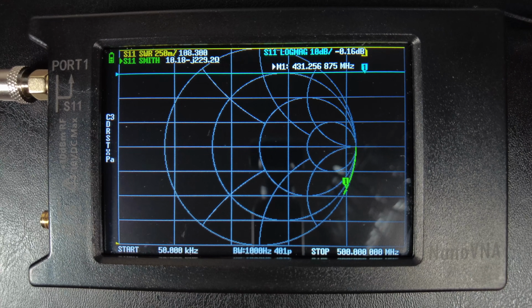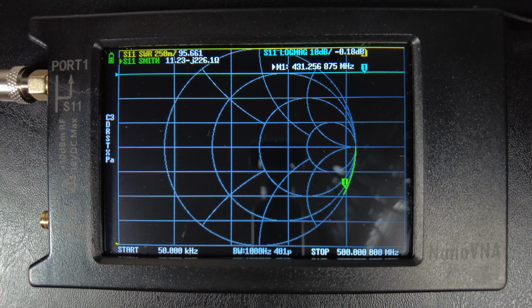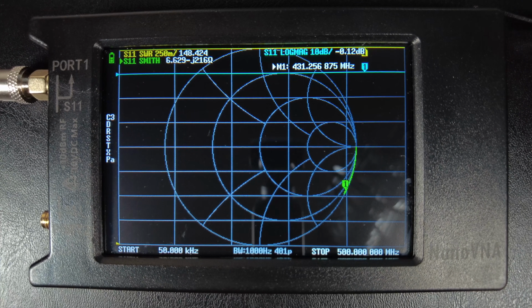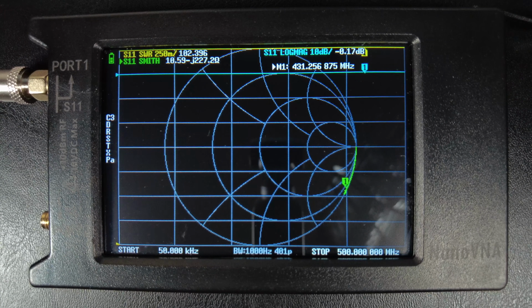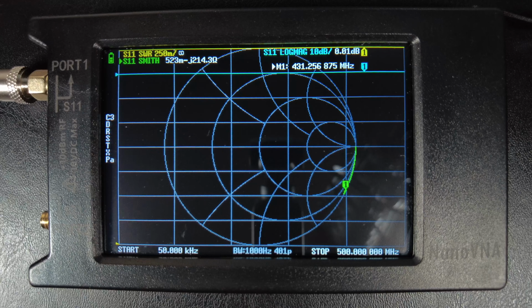that up to 0.7. So since this measurement measures the time it takes a signal to leave port 1 and be reflected back to it, then this is just an S11 measurement. Oh, the other important thing to know is all these measurements are done in metric, so you have to convert if you want to convert to feet and inches. Okay, so now the first step is to set the frequency range. A higher stop frequency will give you better resolution, meaning a more accurate distance, but a lower stop frequency will allow you to measure a longer cable.